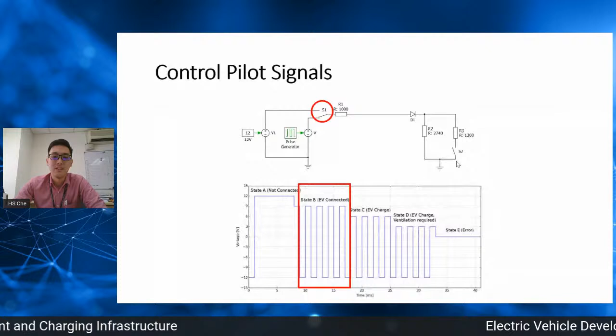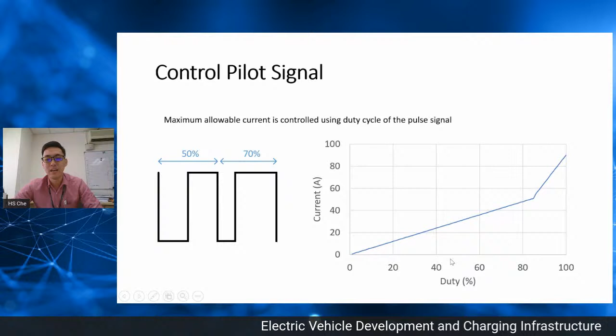The duty cycle means the on time of the pulse. With a 50% duty cycle, 50% of the time the pulse is on and 50% of the time it's off at minus 12, with the on state being plus 12, plus 9, or plus 6 depending on the state. A 70% duty cycle means 70% on time and 30% off time. According to SAE J1772, there's a relation between duty cycle and the current allowed—for example, for 32 amps you'd get around 40 to 50% duty cycle.